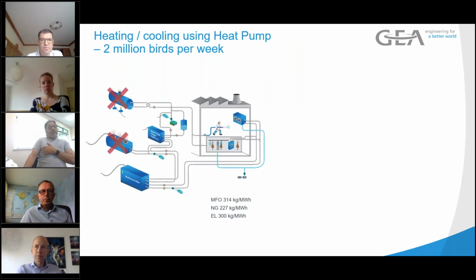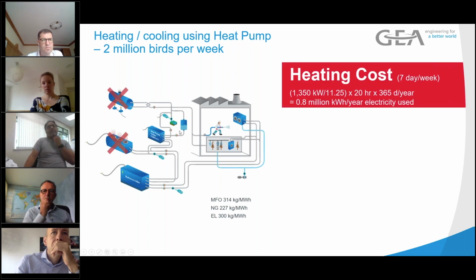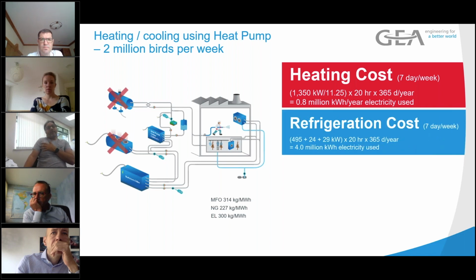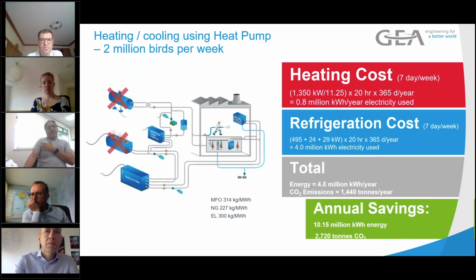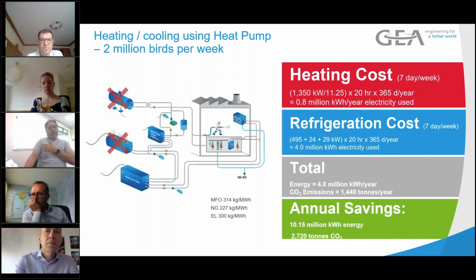What we did there, we just basically added the heat pump to boost the heat that we normally reject via the condenser, which allowed us to turn off 3 out of 4 boilers and half of the condensers, because we're no longer rejecting the heat. So if we then look at the revised figures, we're now only using 0.8 million kilowatt hours a year for the electricity for the heat pump. The refrigeration's about the same. We've reduced fans, but raised the heat pump power. But the combined total has dropped significantly. So it's 10 million kilowatt hours per year and nigh on 3,000 tons of CO2.